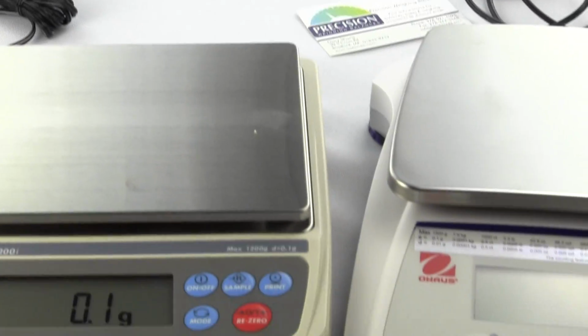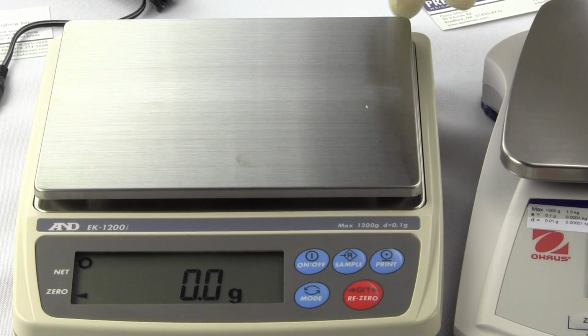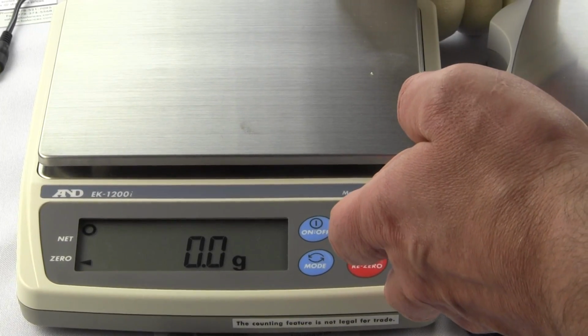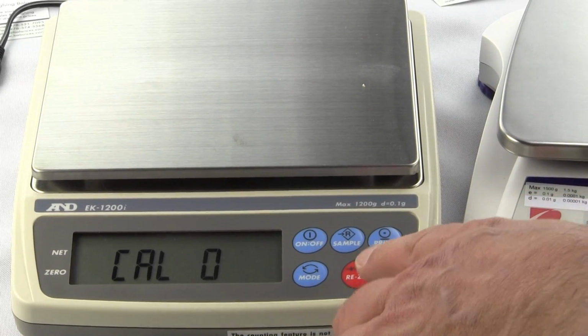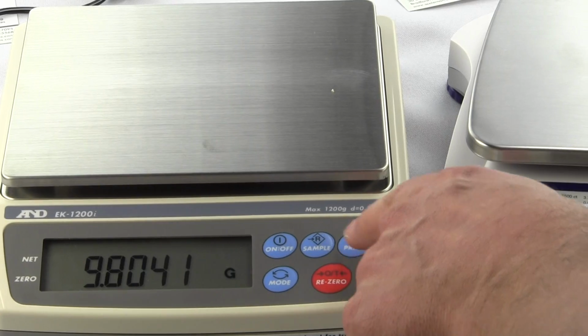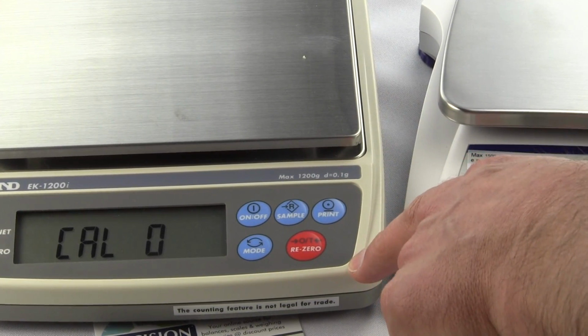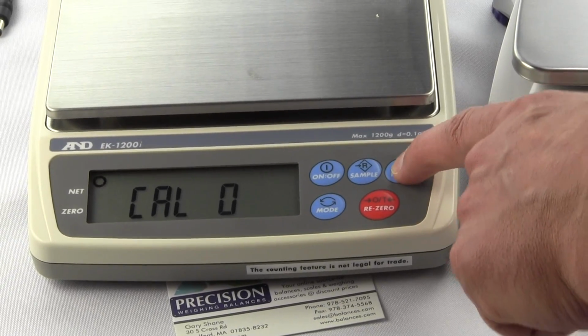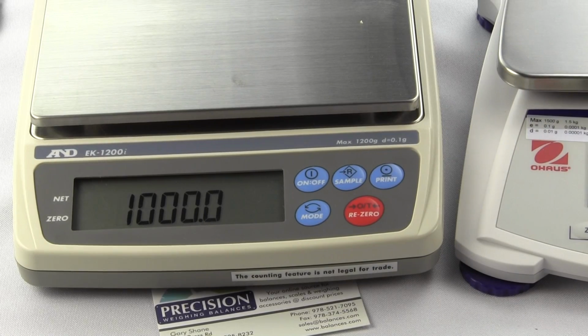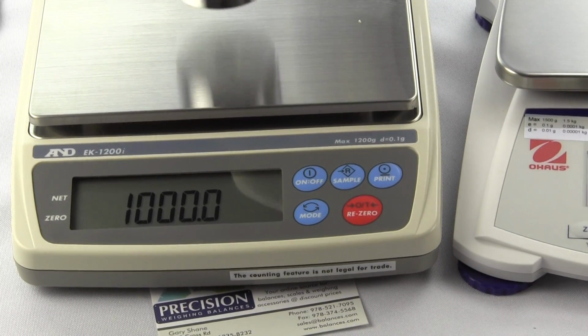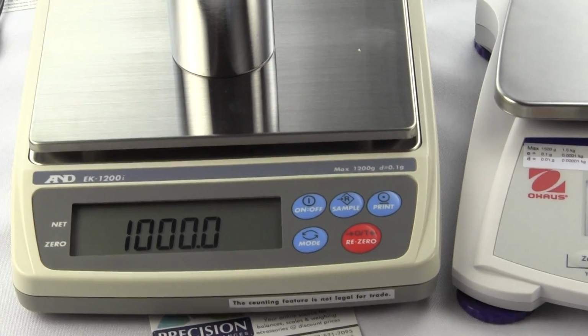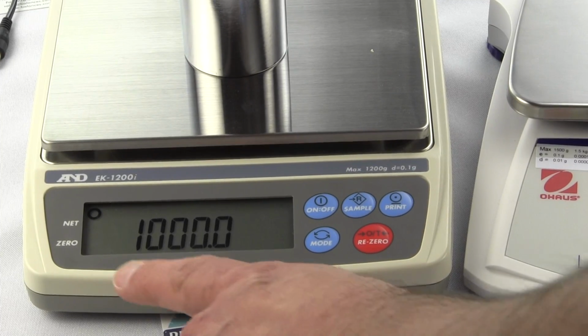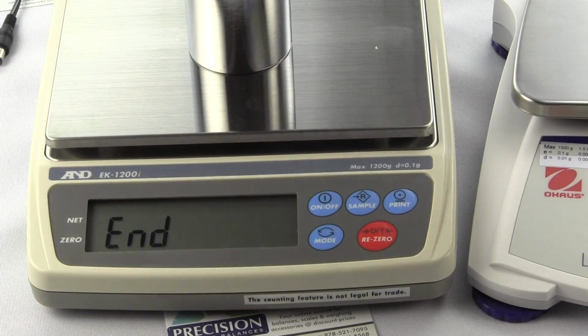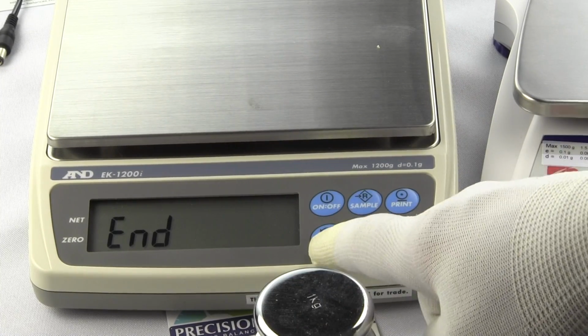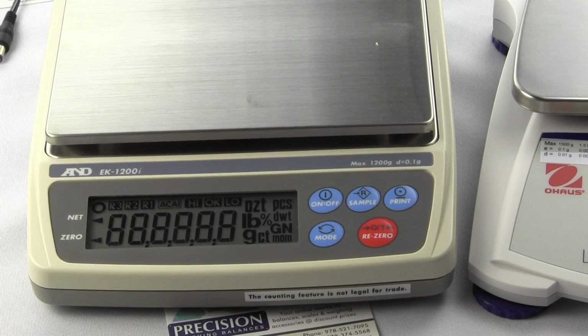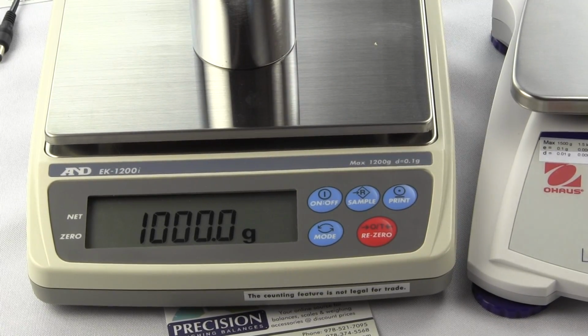So in order to perform the calibration, we want to tare the balance. I have to press the button in the back. You'll see cal. This is for, we can enter the acceleration of gravity, but I've already set it for where we're located. So to perform the calibration, we just hit the print key, and then it's going to flash 1000. Simply put 1000 on it. We hit the print key again. You'll notice in the upper corner there's a stabilization indicator saying that it stored the value, and then we hit the mode button, and calibration is complete. Pretty simple.